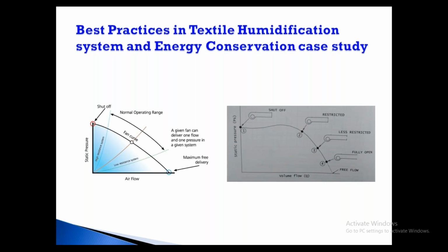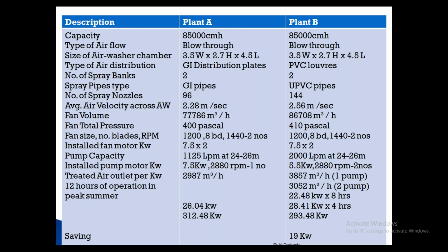If he is giving a certified fan, if he is declaring that our fan at a particular RPM works for this flow and this pressure and takes this much kilowatt, it means they will definitely do the fan testing. Then only will they supply to the customer. If it is a copycat, just the same fan made by pressure casting or die casting, then they will not be able to give the fan chart and other things. So it is a must. In HVAC, heating, ventilation, air conditioning applications, the consultant insists on a fan curve and fan chart from fan suppliers. So that is a must. If you have that fan chart, based on that you can easily find out what efficiency it is working at.